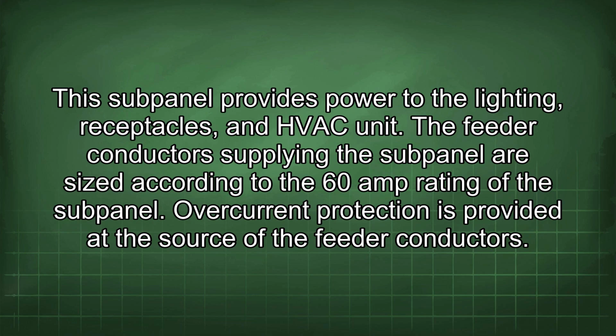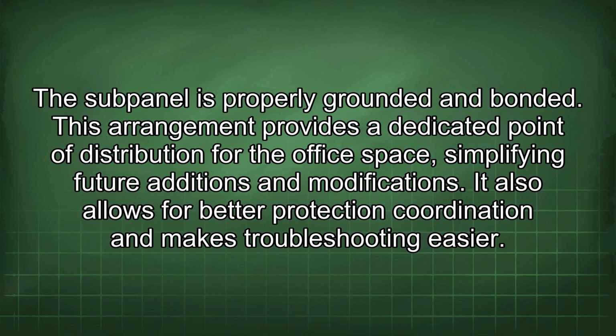The feeder conductors supplying the subpanel are sized according to the 60 amp rating of the subpanel. Overcurrent protection is provided at the source of the feeder conductors. The subpanel is properly grounded and bonded. This arrangement provides a dedicated point of distribution for the office space, simplifying future additions and modifications. It also allows for better protection, coordination, and makes troubleshooting easier.